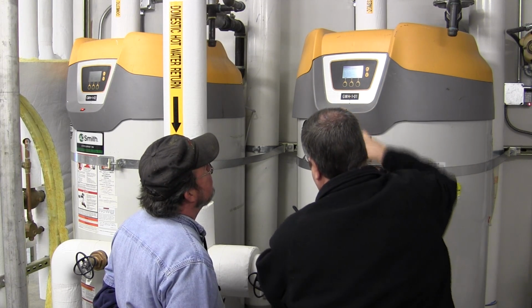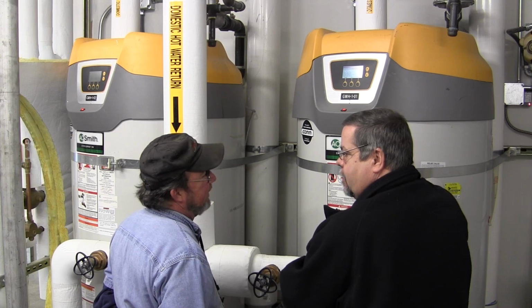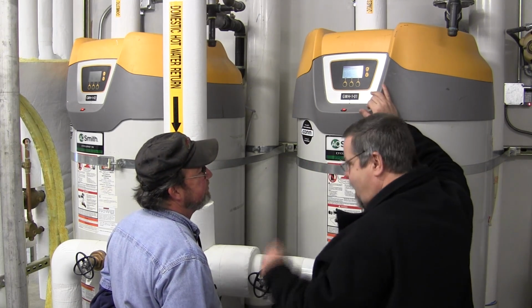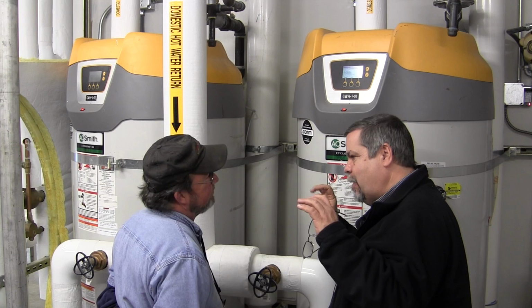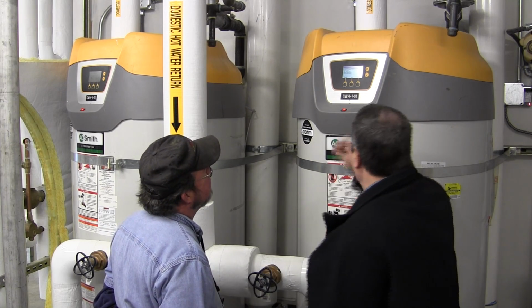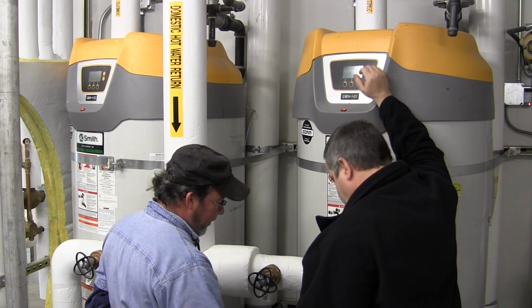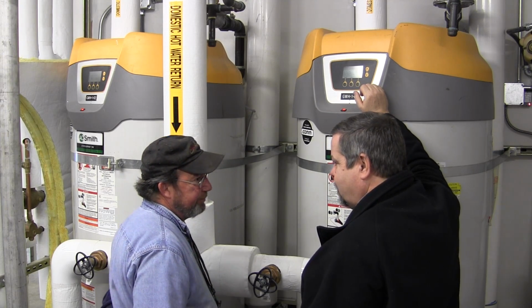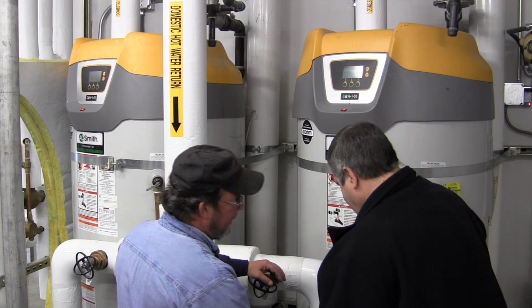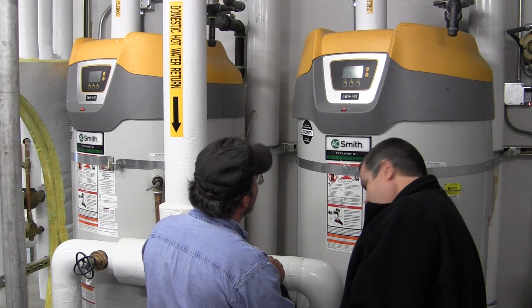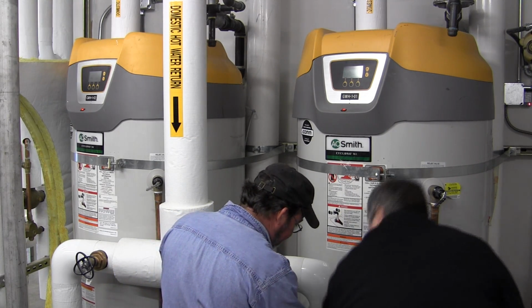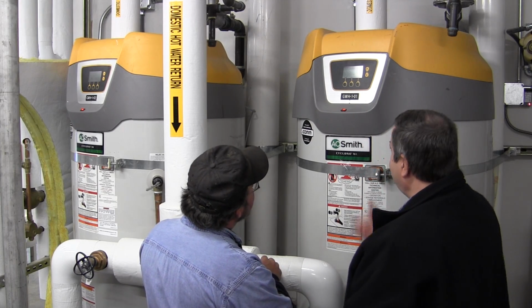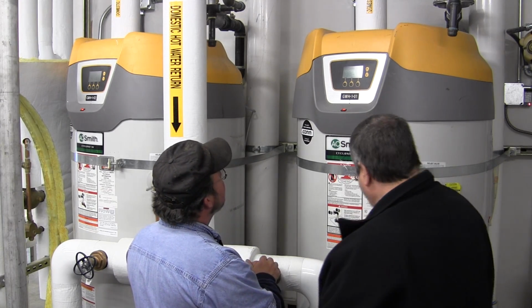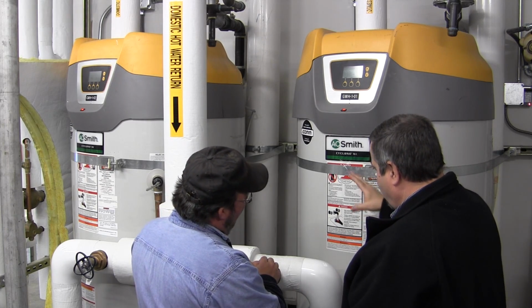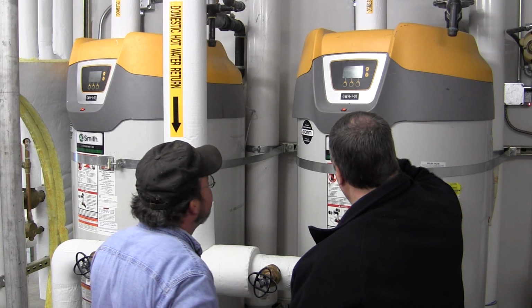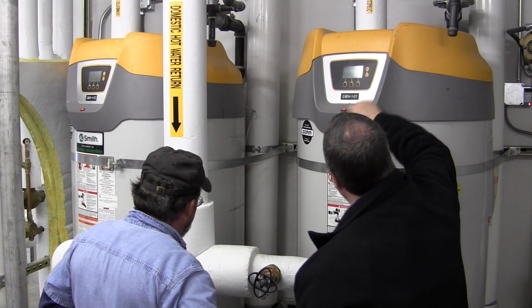So it's sensing 2 things, because as you bring cold water in... Is it going to take an average then? It's not an average. I think technically it's an algorithm. I'm not a math guy, but it's a formula. It programs them into a formula, but without both sensors plugged in, it's not going to work. It would just sense one or the other. That's the one you were talking about that got kicked off. The white thing got unplugged, and it said lower temperature probe. Plugged it in and off it went. It takes the reading up here and the reading down there based on some formula that they figured out to compute the real temperature. They plug it into a mathematical formula in their little chipboard.